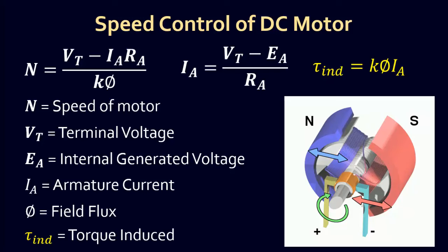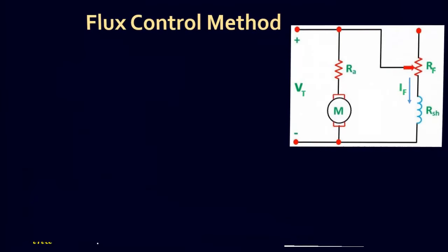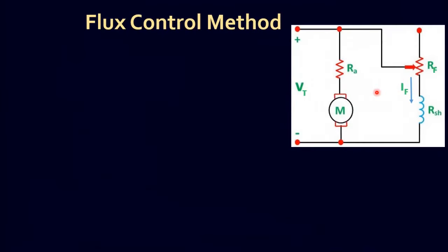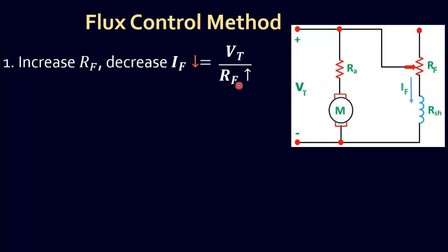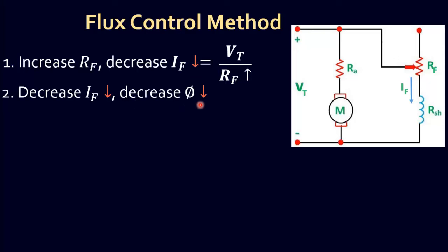Let's get started with the detail of the first method, which is field flux control. We add a variable resistor RF in series with the field winding. As we increase RF, field current IF is decreased according to this relation. As IF is decreased, field flux is also decreased.